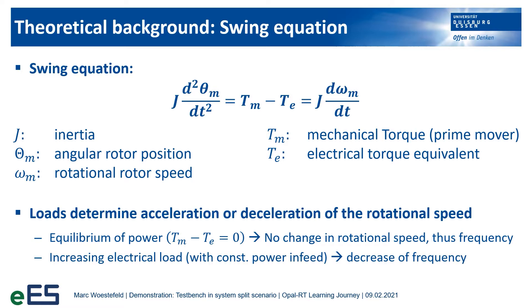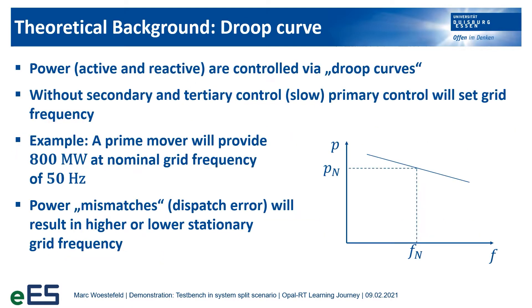But this just tells us whether the frequency will change or not. Without any additional value, it will not give us a specific frequency. This will be done by the droop curve. The droop curve is part of the primary control. Without secondary and tertiary control, it will give us a resulting frequency. Let us look at a power plant with 800 MW of nominal power. In normal operation, its prime mover will provide the needed power with a nominal frequency at 50 Hz.